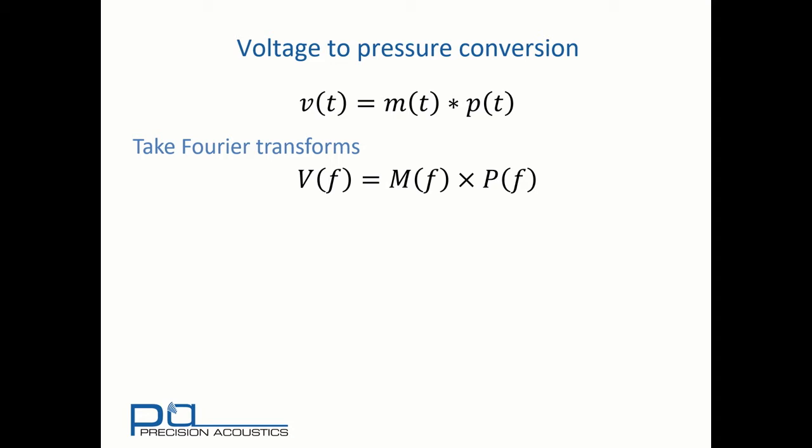One advantage of the Fourier transform is that it allows us to replace a time domain convolution with multiplication in the frequency domain. Therefore, to extract the pressure spectrum, we simply need to take the ratio of the voltage spectrum and the sensitivity spectrum.